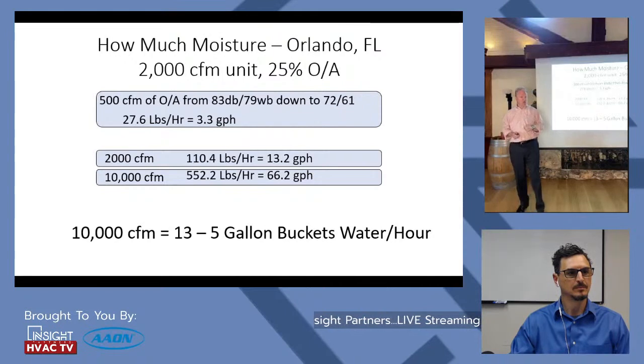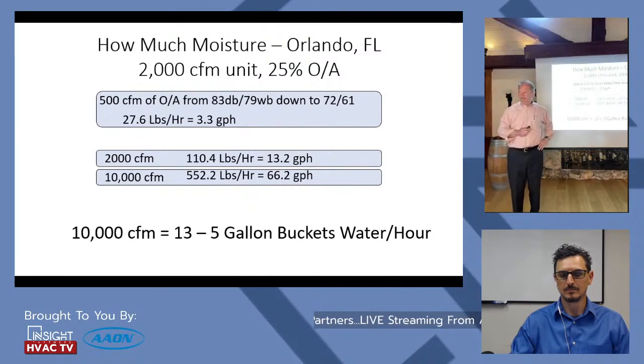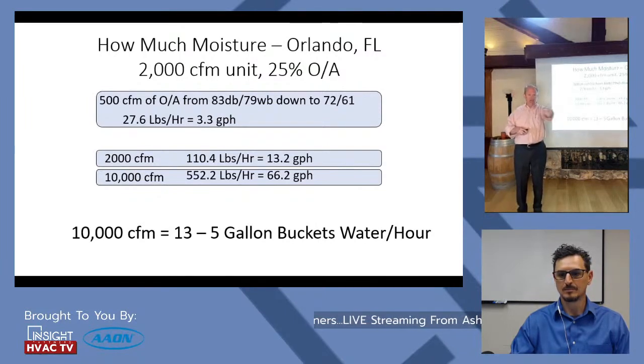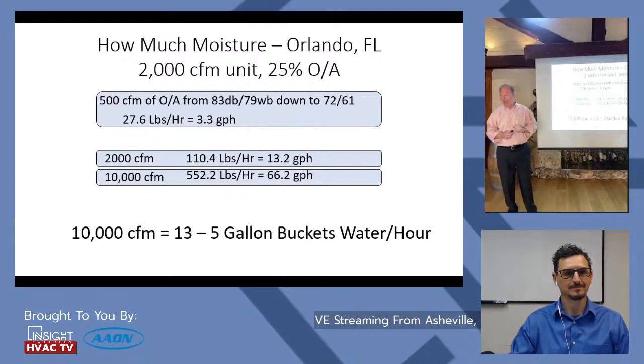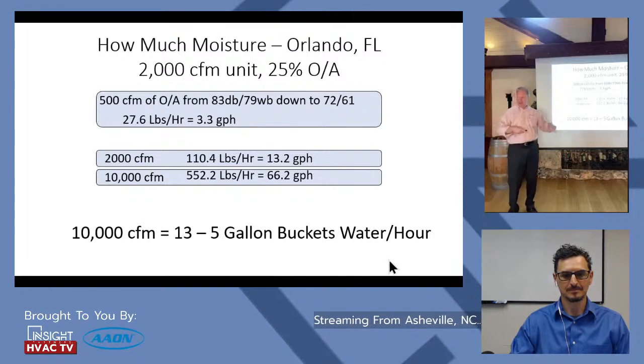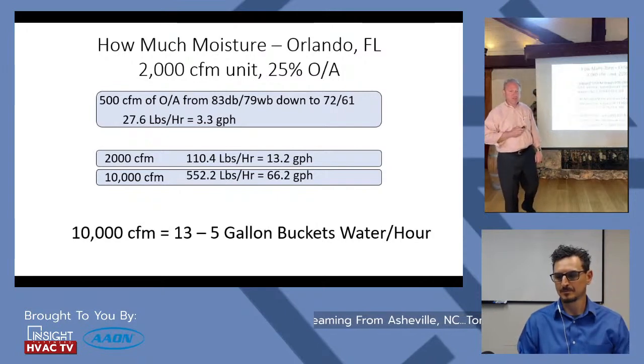Scale that up to a larger building — 10,000 CFM, a good medical office building — and you're talking 66 gallons per hour. That's 13 five-gallon buckets of water thrown into the space every hour on a design humidity day. I had an indoor pool project where the condensate was going to be dumped on a small grass area surrounded by concrete pavement — on a 140-ton pool unit, we were pulling out about 2,000 pounds per hour of condensate. They would have been making a swamp.